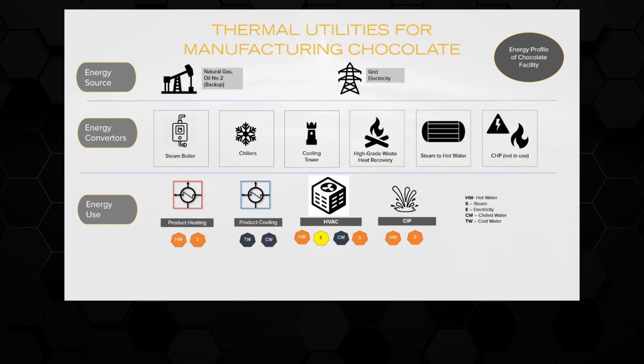Hot water was generated at three temperatures, 110, 140, and 195 degrees Fahrenheit. It was used for product heating in tanks, for tracing praline and fats, and also for the CIP or cleaning process. There are four water-cooled chillers, each of 20-ton capacity, that generate chilled water for product cooling. The chillers and air compressors are water cooled.